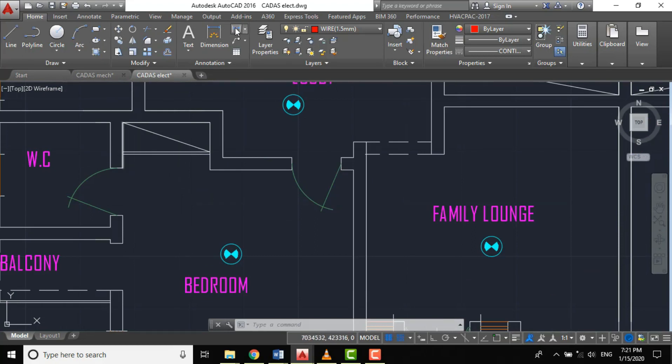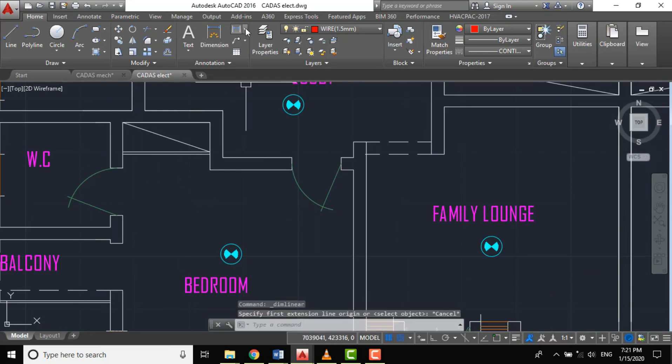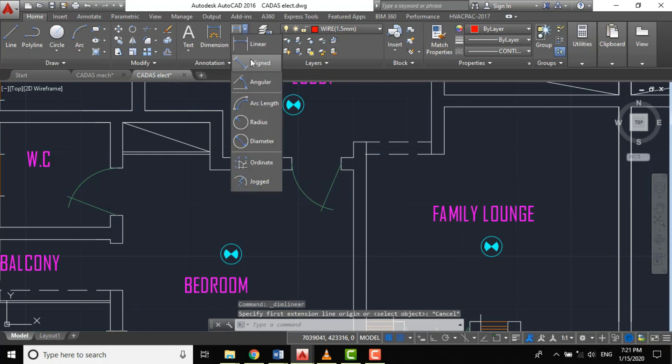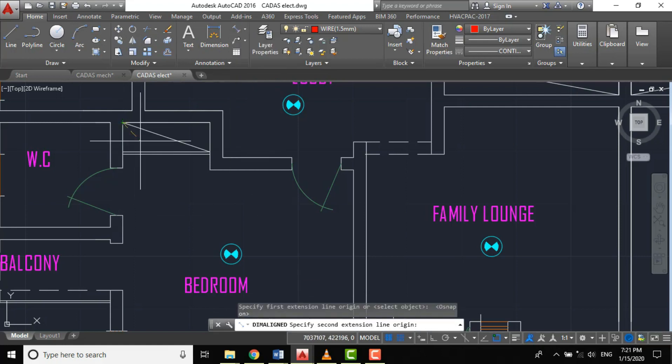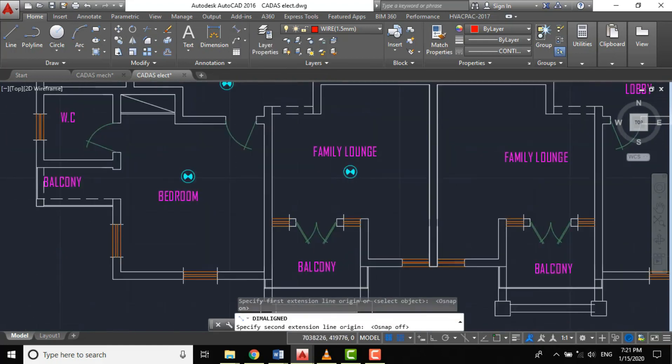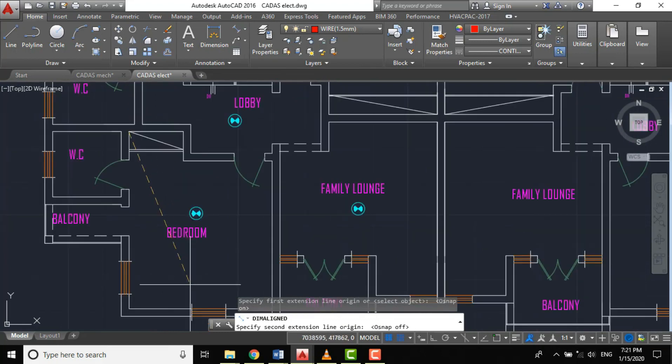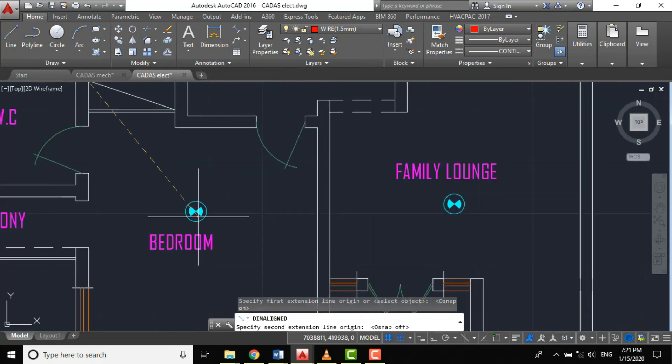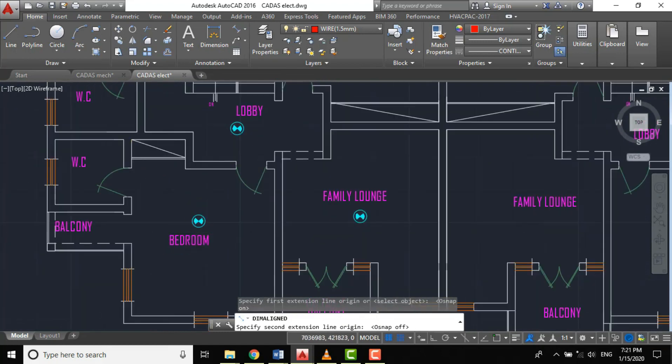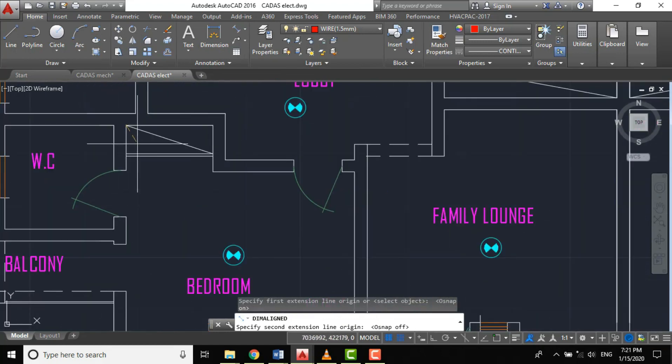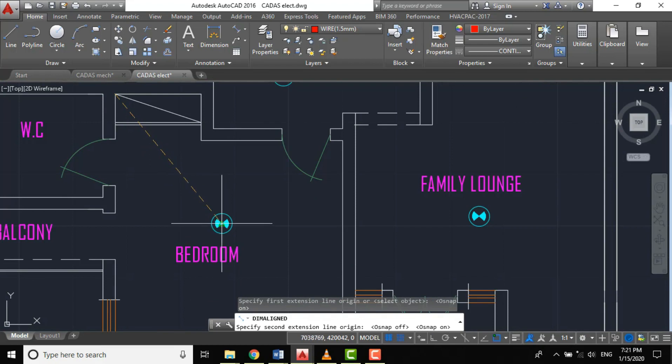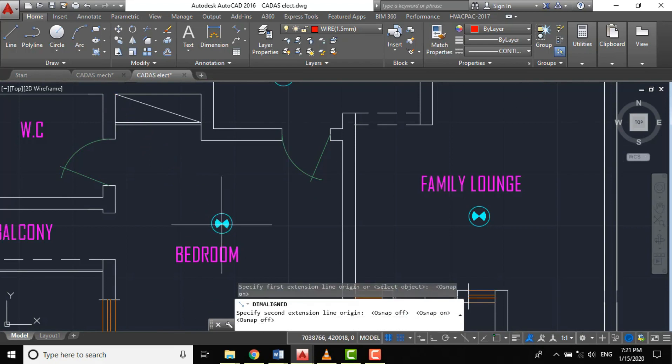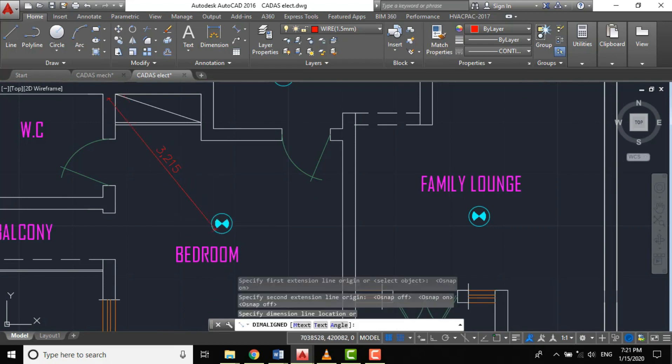So any point in our building must be within the 7.5 meter range. Let's verify this. This is a dead zone, so by taking a dimension from this dead zone here to this midpoint, we just have three meters.